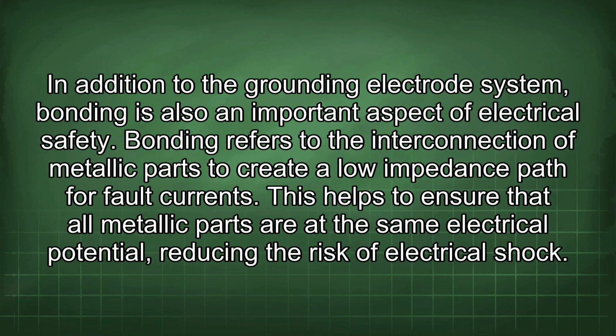In addition to the grounding electrode system, bonding is also an important aspect of electrical safety. Bonding refers to the interconnection of metallic parts to create a lower impedance path for fault currents. This helps to ensure that all metallic parts are at the same electrical potential, reducing the risk of electrical shock.